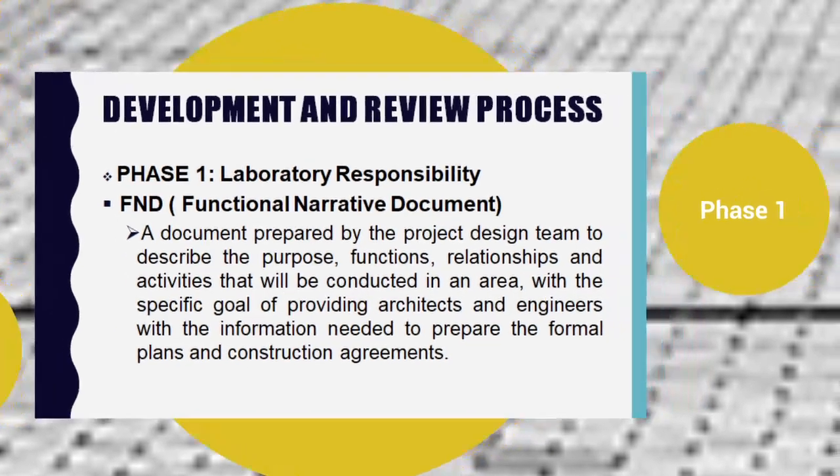Phase 1 is the laboratory responsibility. This is the writing of the FND or the functional narrative document. It is a document prepared by the project design team to describe the purpose, functions, relationships, and activities that will be conducted in an area, with the specific goal of providing architects and engineers with the information needed to prepare the formal plans and construction agreements.